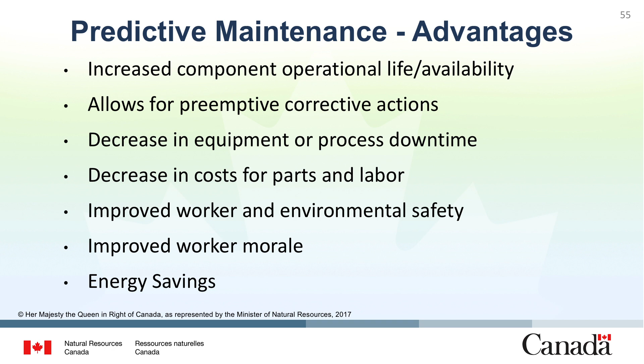If things are operating optimally, if your plant is operating at a high degree of reliability and things aren't breaking, you have a safe environment and your worker morale improves as well. There are also energy savings. If the plant is operating as it should be, the components are running efficiently and effectively, you won't have steam leaks, you won't be blowing through the steam traps, and the boilers will operate at a higher thermal efficiency because you've taken care of issues like scaling.